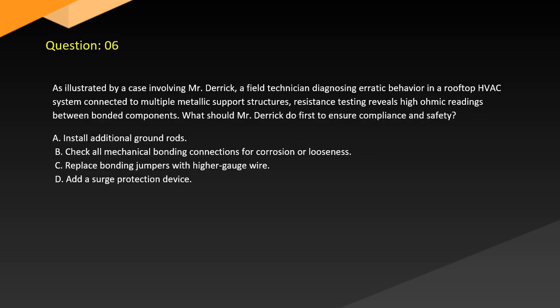Question 6. As illustrated by a case involving Mr. Derek, a field technician diagnosing erratic behavior in a rooftop HVAC system connected to multiple metallic support structures. Resistance testing reveals high ohmic readings between bonded components. What should Mr. Derek do first to ensure compliance and safety?